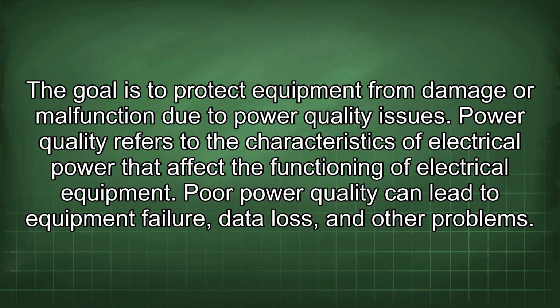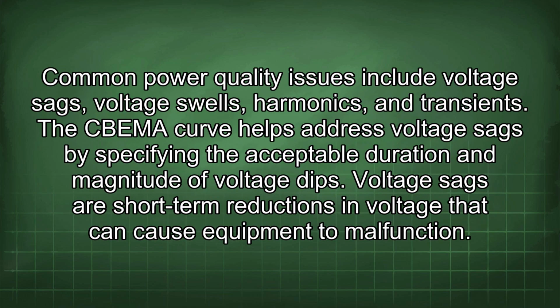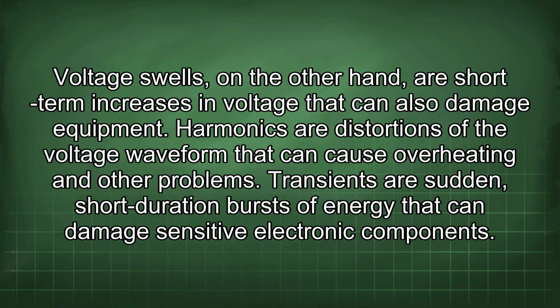Power quality refers to the characteristics of electrical power that affect the functioning of electrical equipment. Poor power quality can lead to equipment failure, data loss, and other problems. Common power quality issues include voltage sags, voltage swells, harmonics, and transients. The CBEMA curve helps address voltage sags by specifying the acceptable duration and magnitude of voltage dips. Voltage sags are short-term reductions in voltage that can cause equipment to malfunction. Voltage swells, on the other hand, are short-term increases in voltage that can also damage equipment.